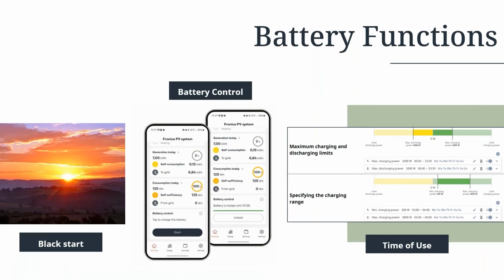If we look at the left-hand side, black start - what does black start mean? It means you have an extended grid outage for whichever reason, and the battery completely discharges overnight through your backup components, so the battery is pretty much flat. The next day, the sun rises, everything gets back to normal. If the system is able to start up from that state - battery empty - and operate normally to support your backup loads, that means it is black start capable. Just be aware, not all inverters and not all systems on the market are able to do that.